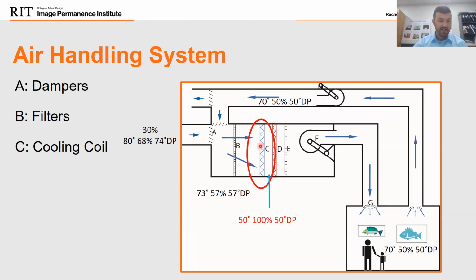So here we were getting some condensation. We reduced the temperature to 50 degrees. We reduced the dew point to 50 degrees. Now we have that 50-degree temperature and dew point. Because of that, our relative humidity now is 100%. So here we have a conundrum, because we can't send this air downstream. We have 50 degrees, 100% relative humidity. Clearly we're at the right dew point, but our temperature and our RH are off. If we send this air downstream, there's potential that we could cause some serious temperature issues, but also mold, depending on whether or not we've blocked some vents. So the first step is to change the condition of the air.